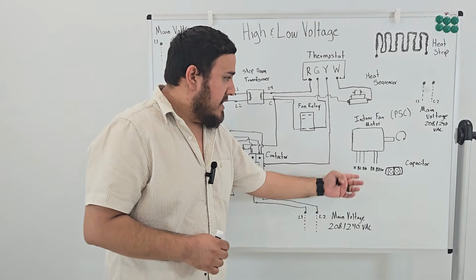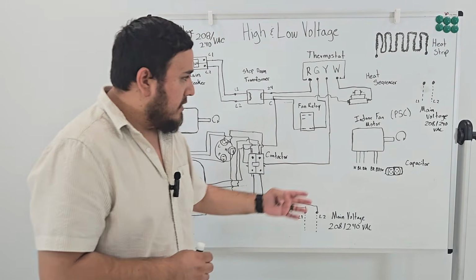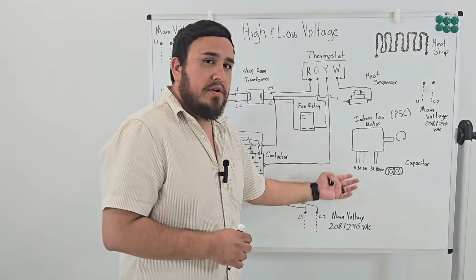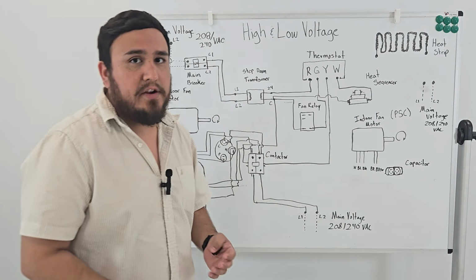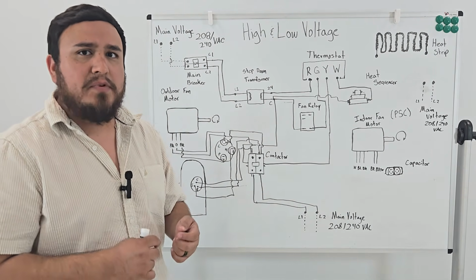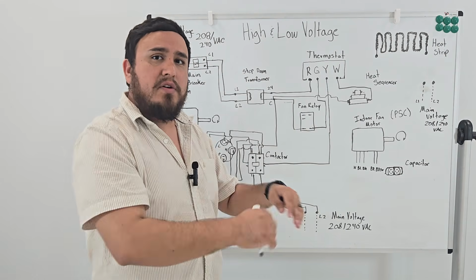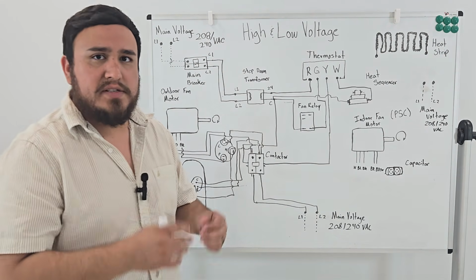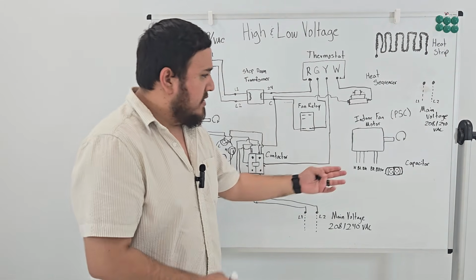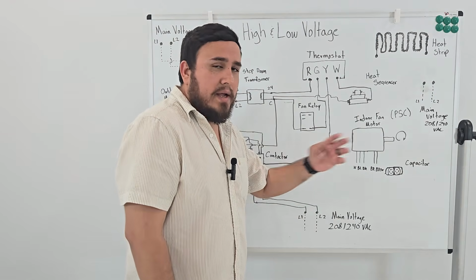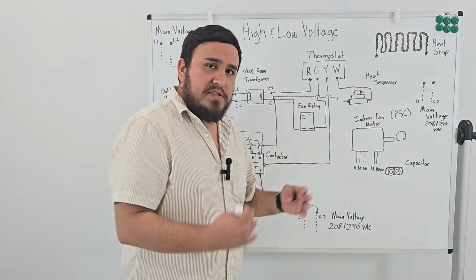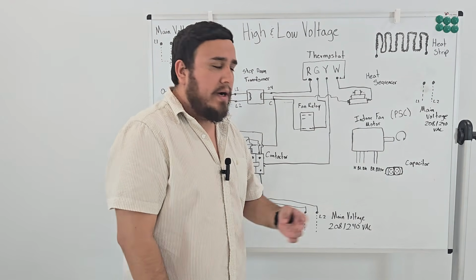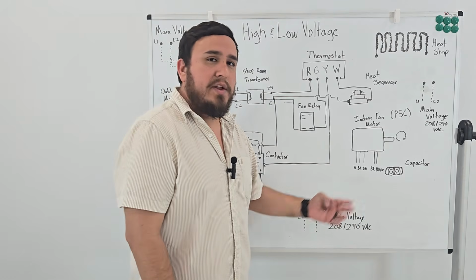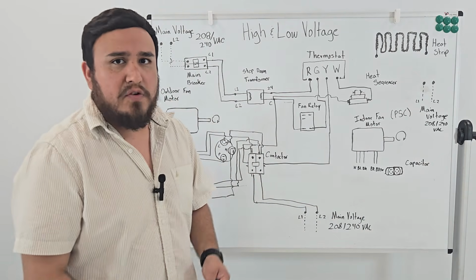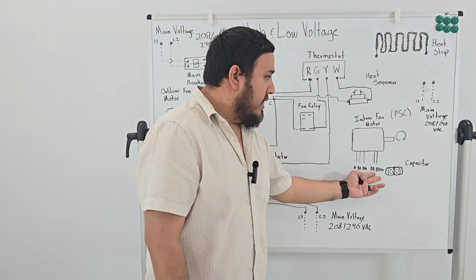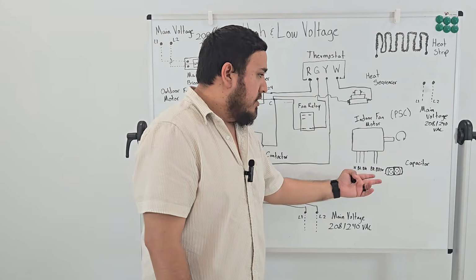Your indoor fan motor is actually supposed to look like this. It's supposed to have 3 different wires. One is your common, and the other 2 or 3 could be your speeds. It all depends on the type of motor that is installed inside your air conditioning system. Every manufacturer is different. So in this case, we'll have a white, blue, and black wire. Let's assume that my common wire is the white wire, blue is your high speed and black is your low speed. And then you have these 2 other wires that will go into your capacitor.